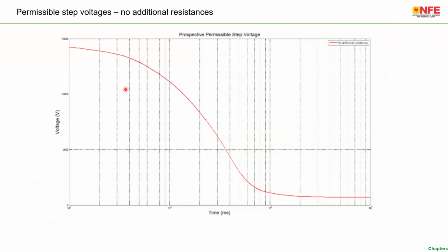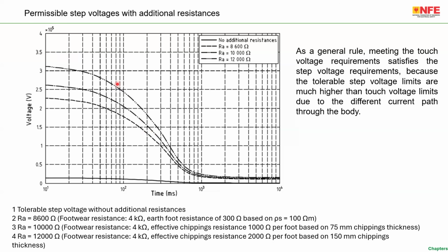Similarly, step potential. For step potential, I have a better graph. As you can see, a 115 volt touch potential is equal to 2800 or 2850 volt step potential for creating a similar ventricular fibrillation as 115 volt left hand to feet touch voltage. The step voltage here, let's say for example 2800 or whatever, but you see 2 into 10 to the power of 5. Now, with added resistances, for example footwear and PPEs, the permissible value of step voltage also goes up. So we have to consider the condition where a person barefoot, bare hand is operating, or the location is restricted to people with PPEs such as gloves and shoes. So all these subjects are to be considered when we talk about this particular subject.